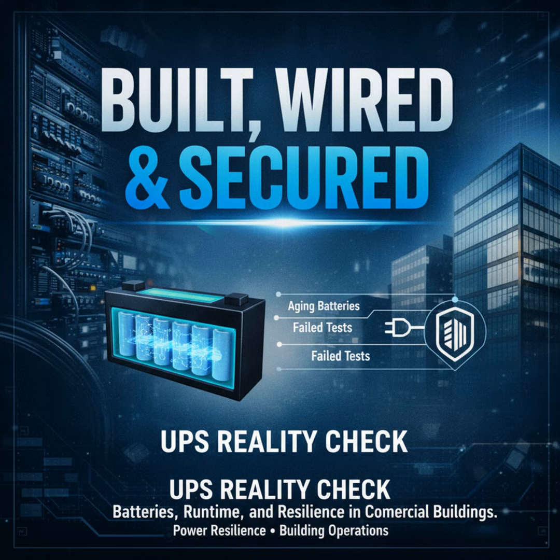Parallel UPS strings can provide immediate failover, but they require matching equipment and coordinated maintenance to avoid common mode failures. Staged redundancy, where one UPS supports critical load and another picks up non-critical loads, can be more cost-effective, but it needs clear load prioritization and automated transfer logic. Again, document the priority map and test failover paths. If you don't know which loads will be shed or kept during transfer, you can't reliably predict tenant impact. That's fine until it fails. Then tenants feel this immediately.